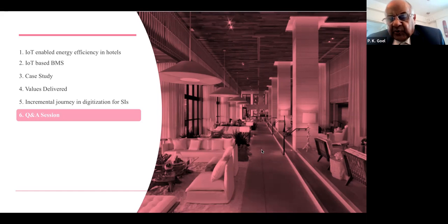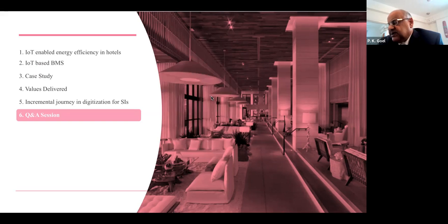I will pose one more concern the HVAC fraternity has had, or a need they want: the coefficient of performance, first of chillers and then of the air conditioning system. Coefficient of performance is defined as kilowatt of cooling divided by kilowatt of power. Obviously it keeps varying on a system, and you can average it over a particular period of time, and you can have a cumulative number every month or so.